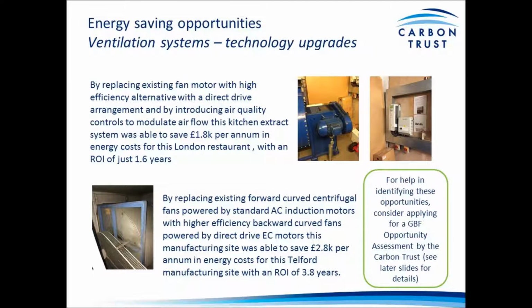And we also provided or recommended they install a kitchen air quality control system. This worked in conjunction with the existing inverter variable speed drive controls to modulate the speed of the fan based on the internal air quality in the kitchen. This particular installation reduced the energy costs by £1,800 per annum, a return on investment of just 1.6 years. So fantastic investment and saving there with relatively straightforward measures.